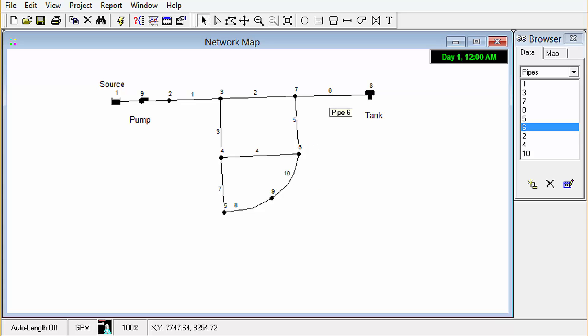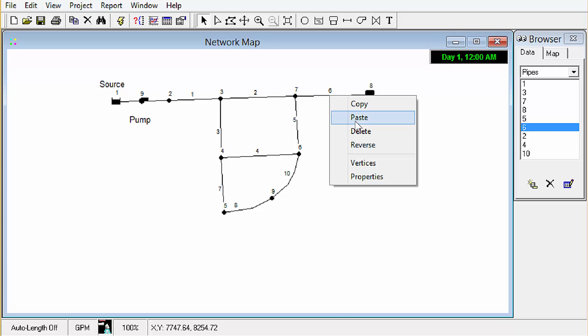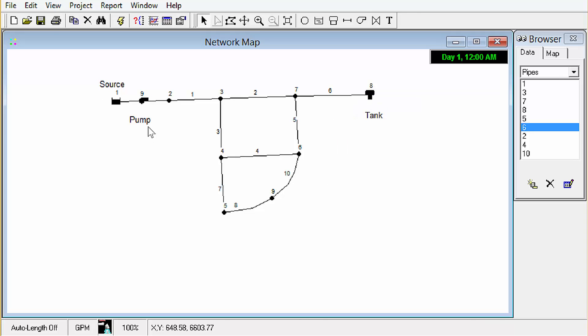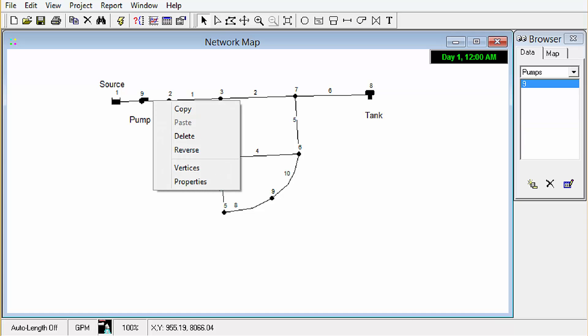Another thing to show is if we select a link and right-click it we can also reverse that. So that's important for links that are control valves, for pipes that are check valves and obviously pumps. We would need the direction of those to be correct. So for example if we were to draw this one from node 2 to node 1 that would be incorrect in this situation and we could reverse that just by right-clicking on the link and clicking reverse.